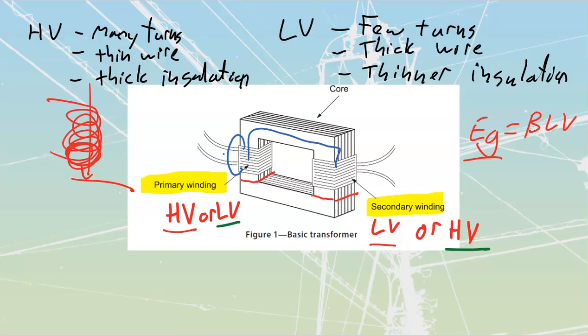The retentivity, the resistance that they're going to have as well. The resistance one does make a difference as well, because it is I squared R. So if we go with the higher value of resistance, we are going to have less watts of heat dissipated by any circulating eddy currents inside of the steel. All right, let's talk about transformer efficiency.